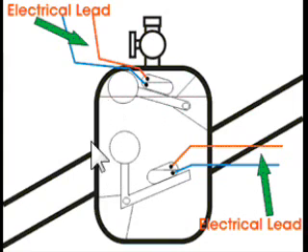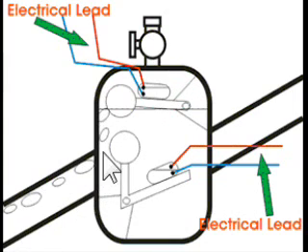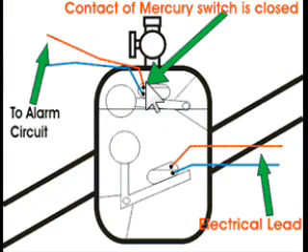The gases produced due to decomposition of transformer insulating oil will accumulate in the upper part of the Buchholz container which causes fall of oil level in it. Fall of oil level means lowering the position of float and thereby tilting the mercury switch. The contacts of this mercury switch are closed and an alarm circuit is energized.